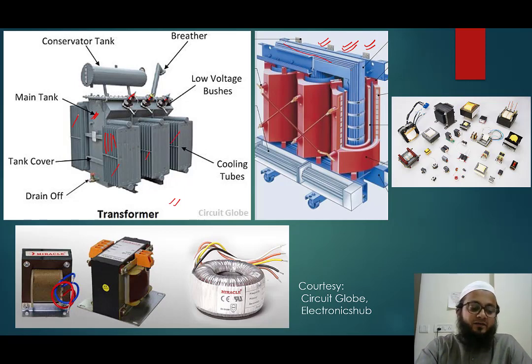These fins are used for the cooling of the transformers, and the one which is shown here is the conservator tank. Sometimes the oil expands, and in summers the volume expands, right? So the extra transformer oil is pushed into these conservator tanks. Okay, and this is the breather. Sometimes some gases are formed, so these breathers help in breathing out the unwanted gases which are produced in the main tank of the transformer.